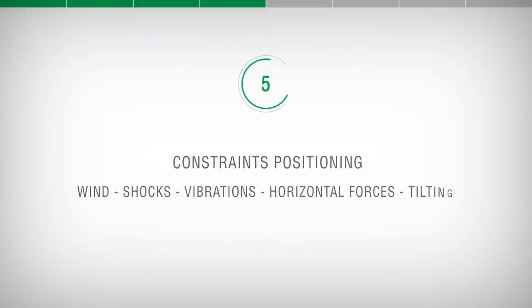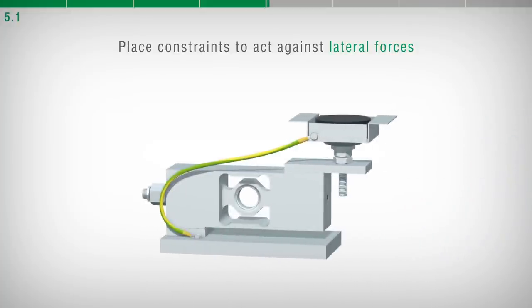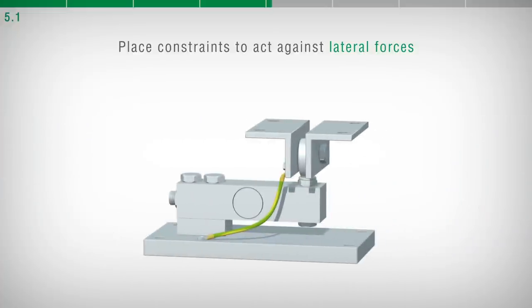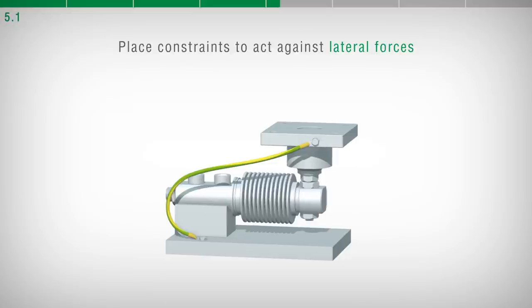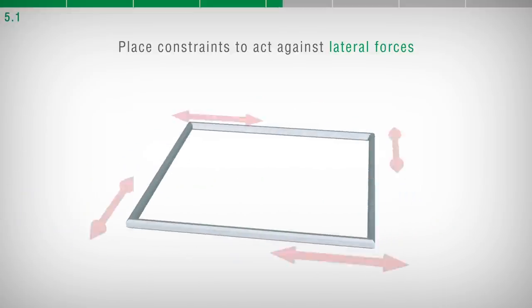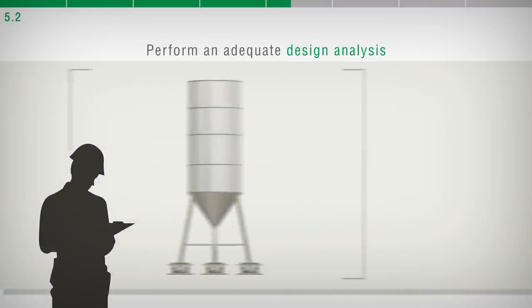Constraints positioning: Wind, Shocks, Vibrations, Horizontal forces, Tilting. Several mounting kits are available. Their purpose is to obtain a correct installation of the load cell and the maximum reliability and precision, compatible with the mechanical, electrical and pneumatic connections on the structure to be weighed. In weighing systems with multiple load cells, it is recommended to place constraints to act against any lateral forces.